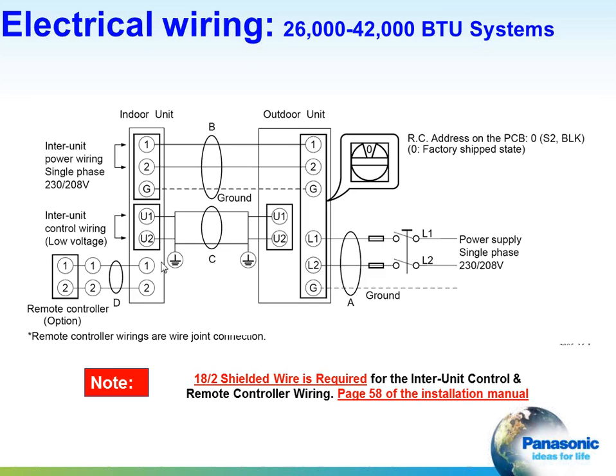Electrical wiring for the Pac systems. Again, this is your 26 through 42,000 BTU systems. You're going to run your power supply, again, 208/230 single phase, using 12 gauge stranded to L1 and L2. And again, the indoor units are powered off the outdoor units. So you have your terminals 1 and 2 up at the top of this diagram, and your ground. Use 16 gauge stranded there. And then for control wiring, if you use that particular control, use single pair shielded cable.